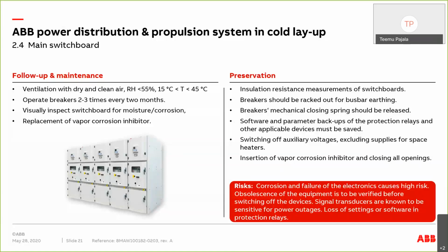One highlight on the risks are the signal transducers. Those are known to be a little bit sensitive to power outages. It depends on the manufacturer and age and all kinds of things, but in general, it's possible that when power is switched off and then after some time switched on, the signal transducers can fail. So special attention on those, mainly to have the spares when they have been switched off.